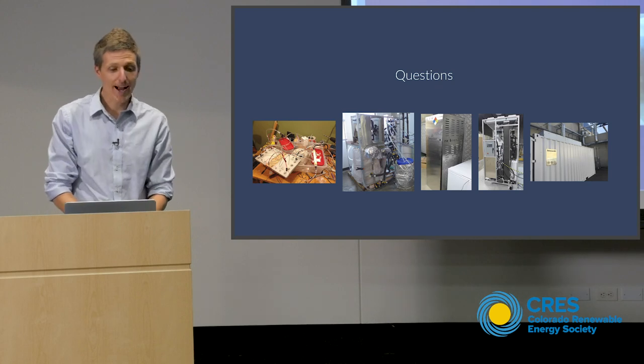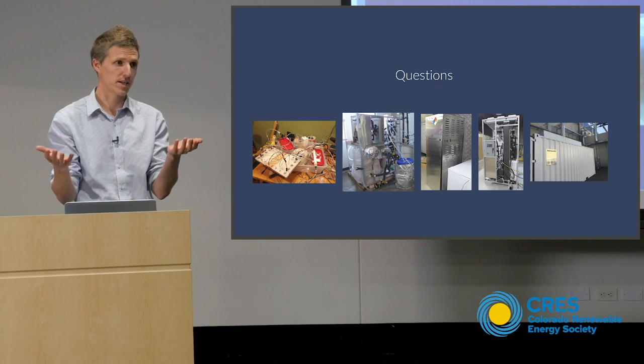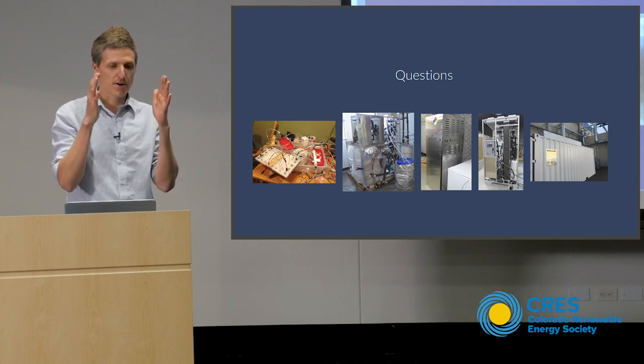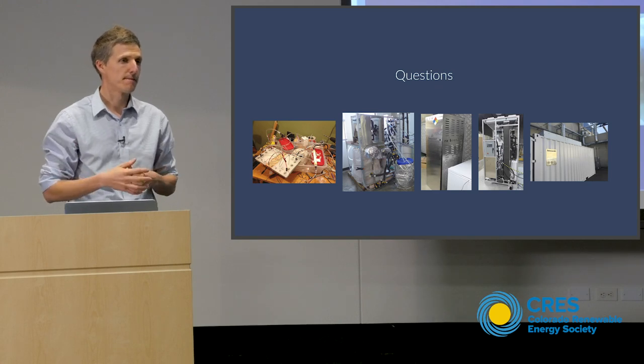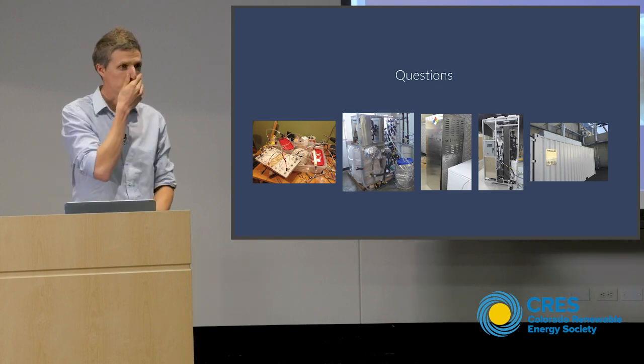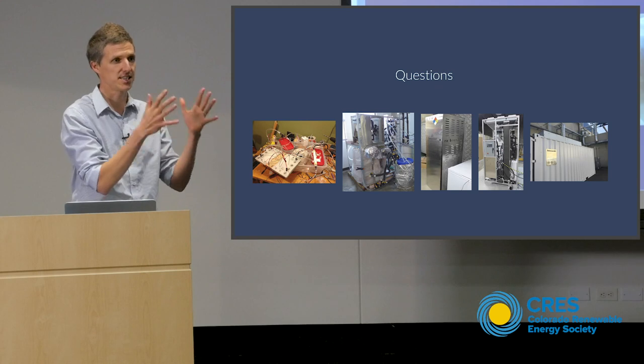In a supermarket you're actually much more incentivized to do electrical arbitrage. The system generates value doing thermal arbitrage or electrical arbitrage or a combination. By arbitrage we mean there is some hour of the day where it's very valuable to either be discharging a lot or not consuming any electricity — essentially using storage for off-peak hours. At a blast freezer all the value is thermal arbitrage — they need these giant peaks. At a supermarket they have a very, very steady load and it all turns to load shifting.